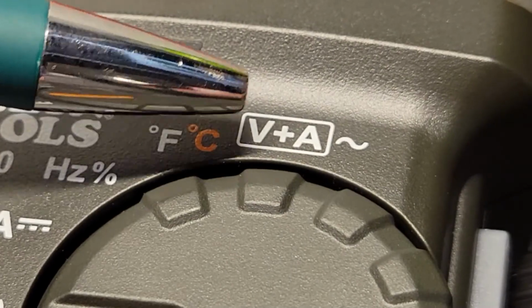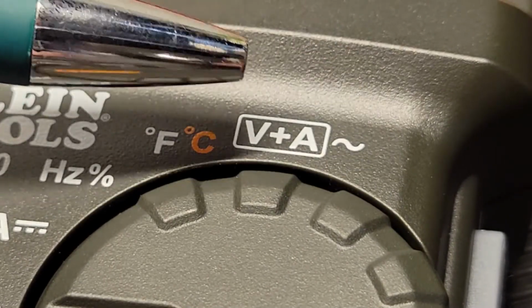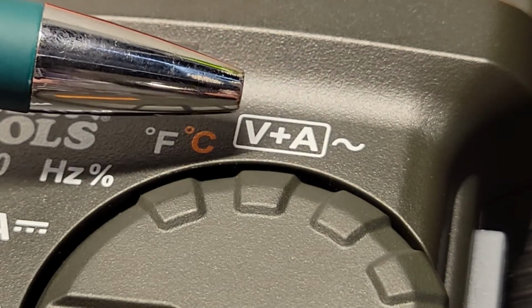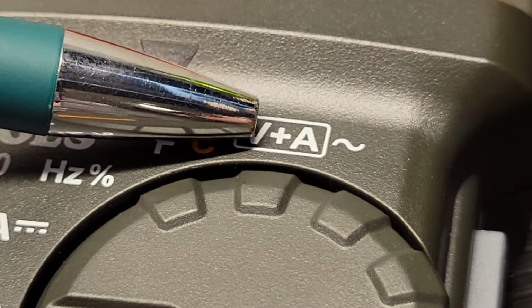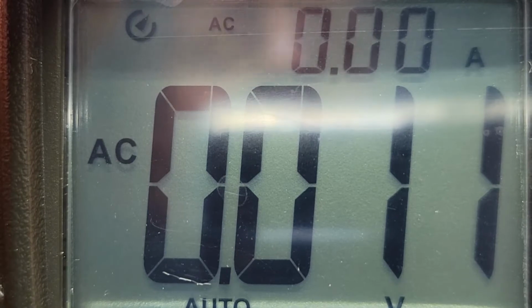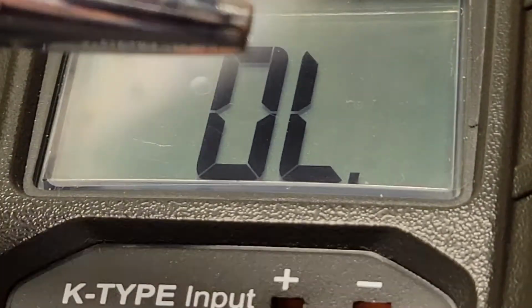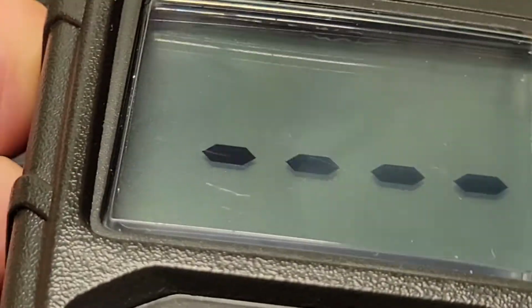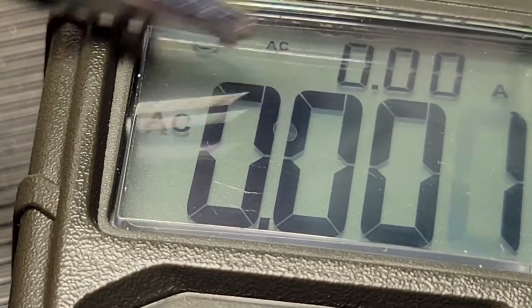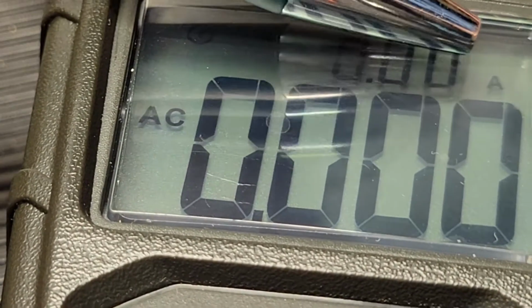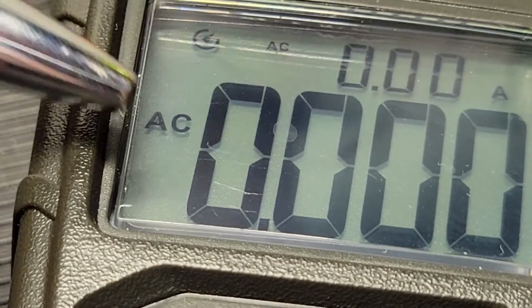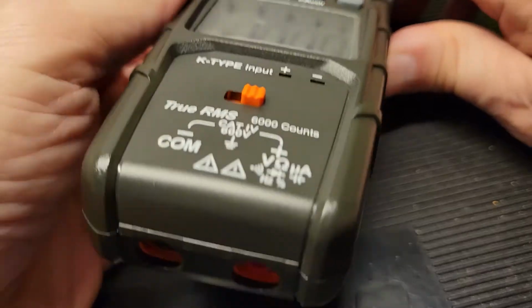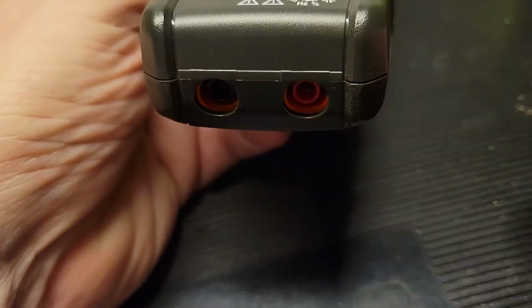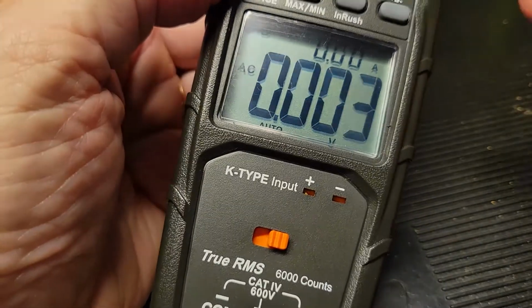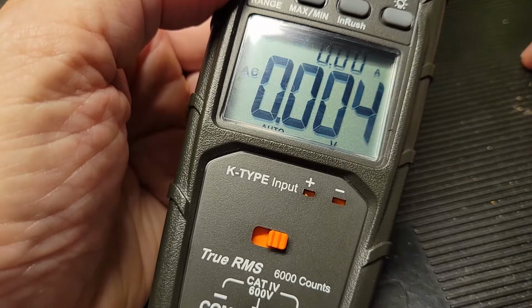Finally, at the top, we have V plus A with the sine. So we know that this means alternating current. So in this case, we can get a reading of voltage plus amperage displayed simultaneously. So what you're going to do is you're going to read current up here. On your display, it's going to show you two numbers. You're going to have your amperage, denoted here by an A, up on top, and then voltage is going to be read down here. And in order to read the voltage, you're going to have to plug in the probes so that you can get that measurement. But it will display voltage on the bottom and amperage on top simultaneously.